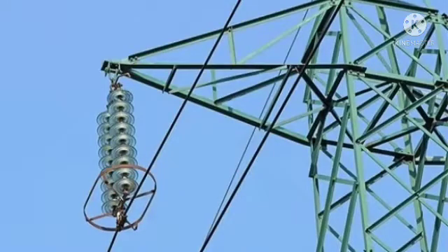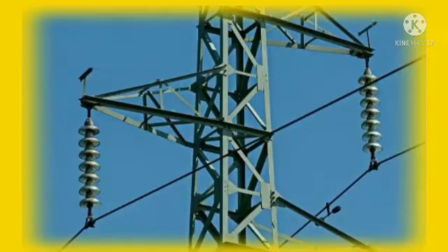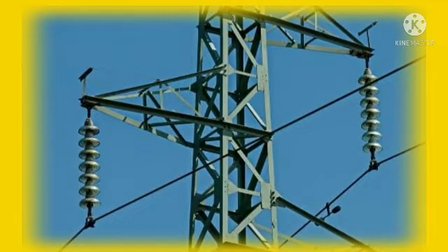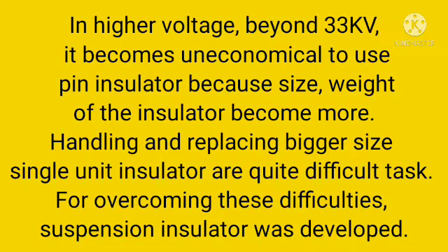Today we discuss suspension type insulators. At higher voltages beyond 33kV, it becomes uneconomical to use pin insulators because the size and weight of the insulator become very large, and handling and replacing such bigger single-unit insulators is quite a difficult task.